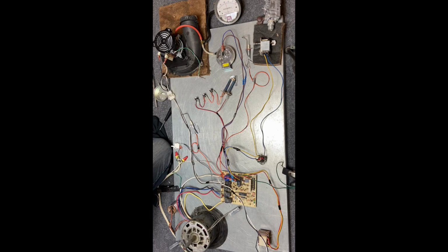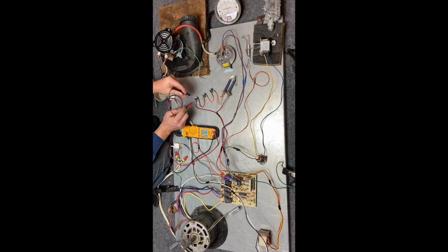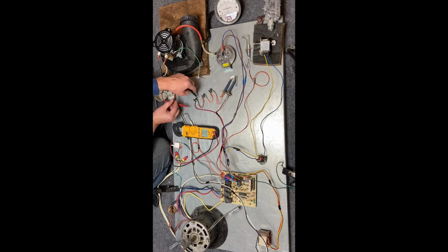Now when we go to the customer's house, what we want to do is look at the control board and see what kind of code it's blinking. Here it's blinking a very specific code. In this case, we can check all these limits individually with voltage. So I have my meter on voltage, and if the switch is closed, it should read 0 volts. And if the switch is open, it should read 24 volts. So if I check across this switch here, reading 27 volts. 27 volts, we know that switch is open.